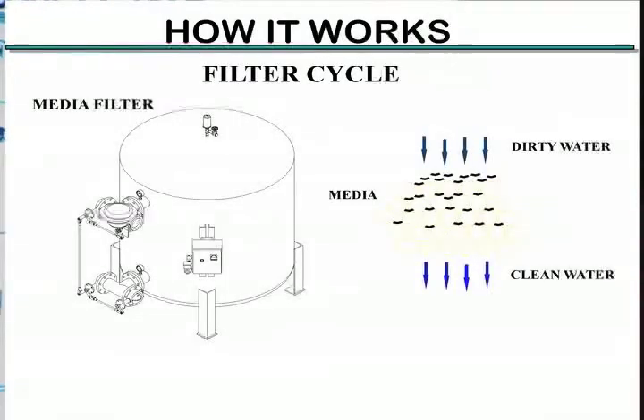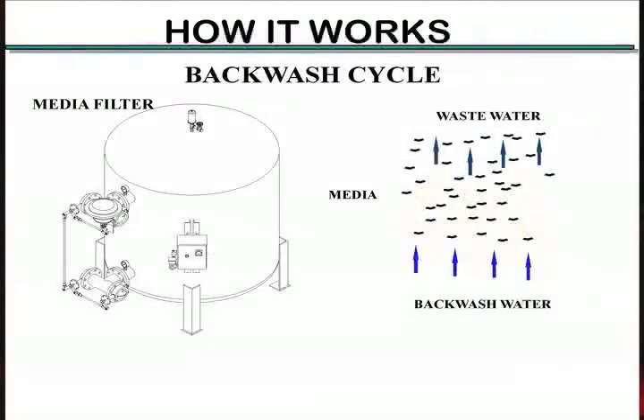In normal operation, the water goes through the media and comes out clean. The particulates are left in the interstitial area between the grains of whatever the media is. To backwash, the water runs the other way — back through the media, it lifts the media up, the particles caught in the media get taken out, and that water is taken out to drain. The particulate matter gets taken out with it.